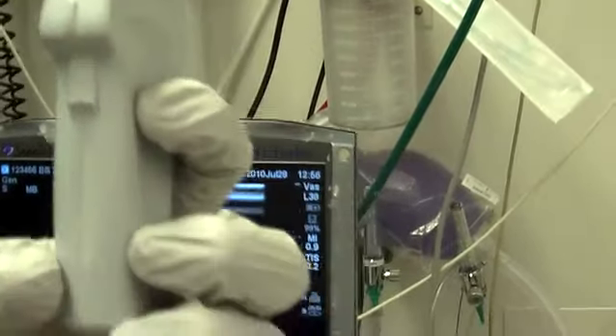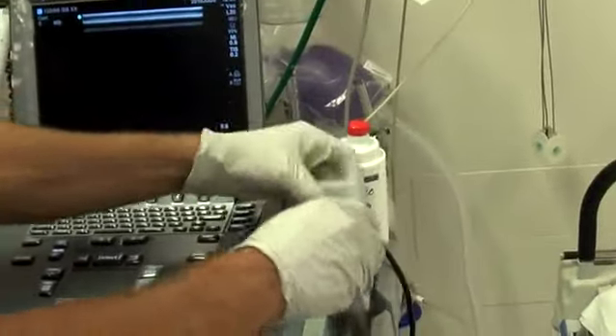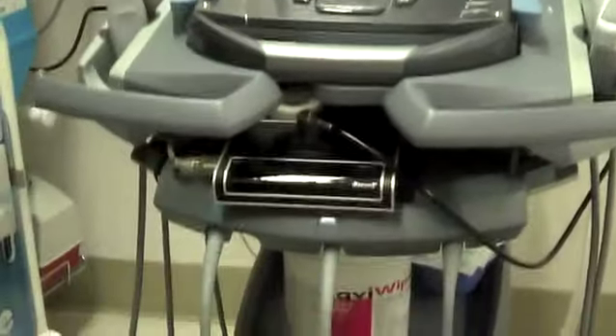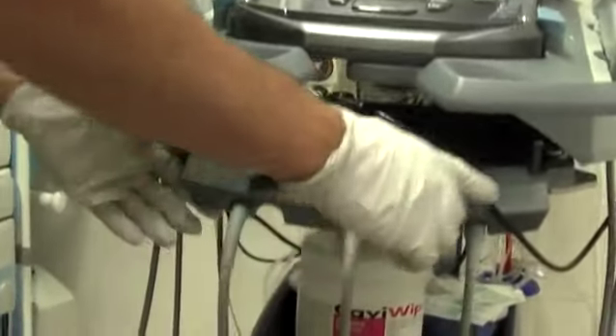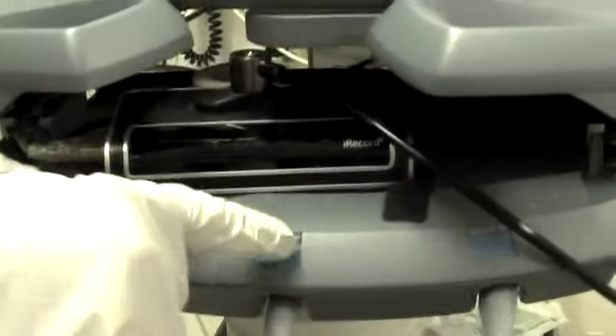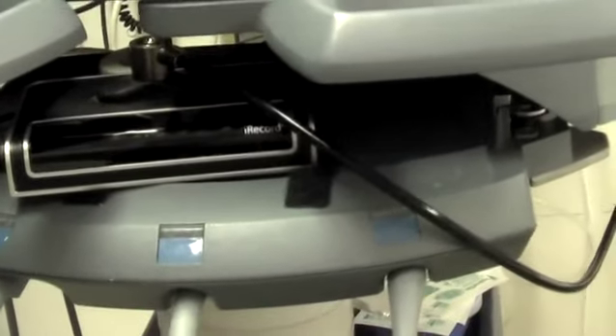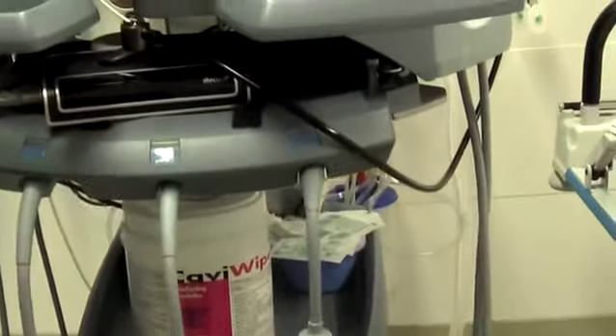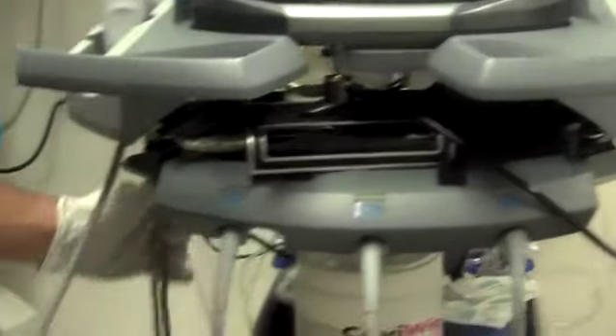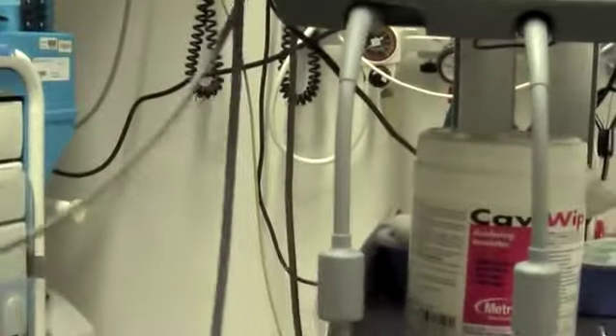How do we disconnect them? So you want to use a probe that's not currently connected to this three-way selector. And as an aside, in order to change which probe you're using, you just hit the button above the respective wire. Let's say, for example, that we would like to use the endocavitary probe, and it's not plugged in currently. So if you look underneath, there's a latch here that pulls down. Give it a turn, 90 degrees, and it'll detach.